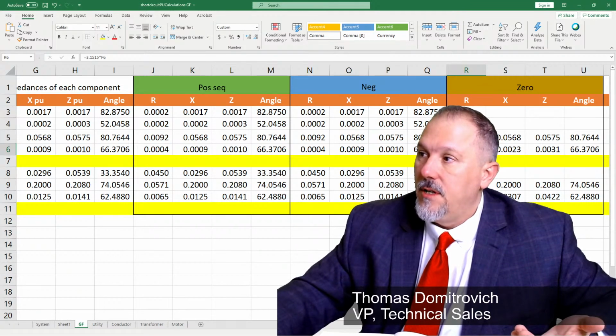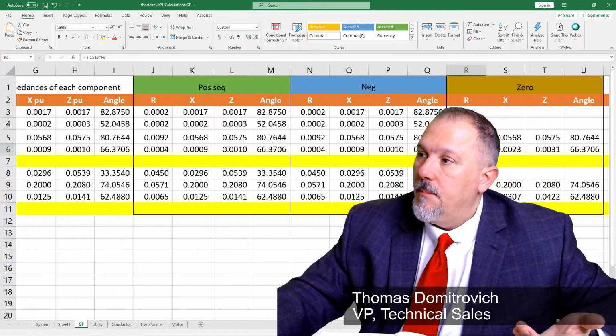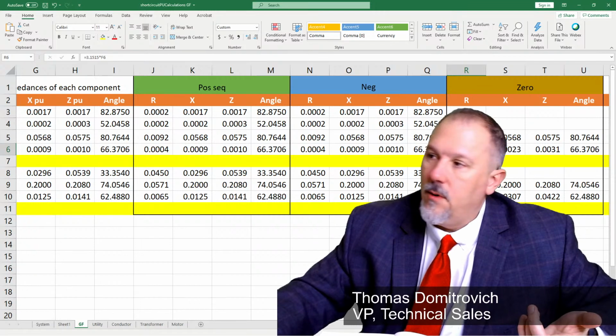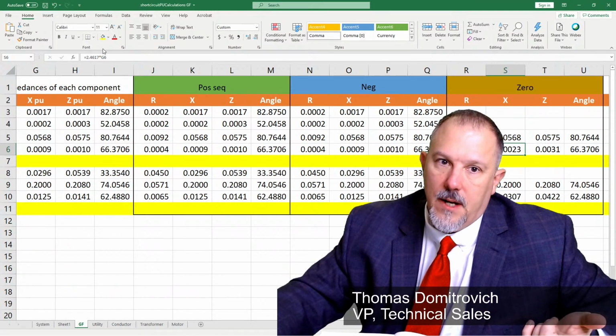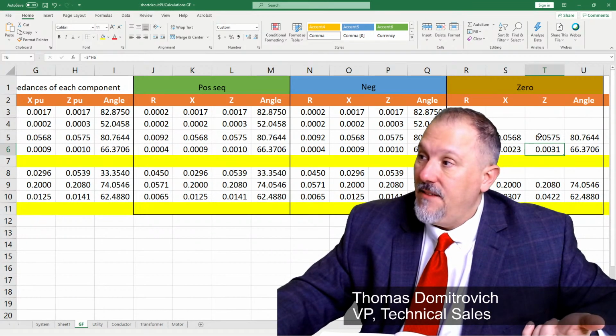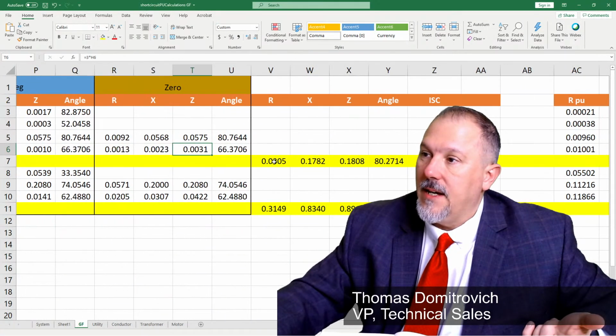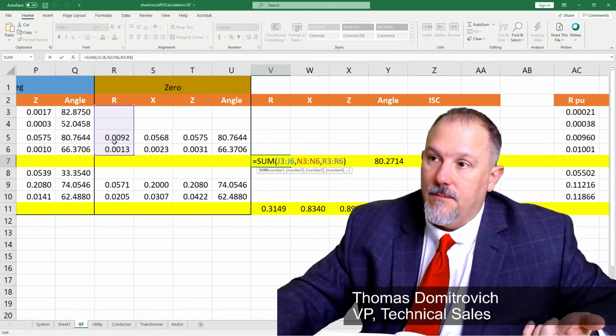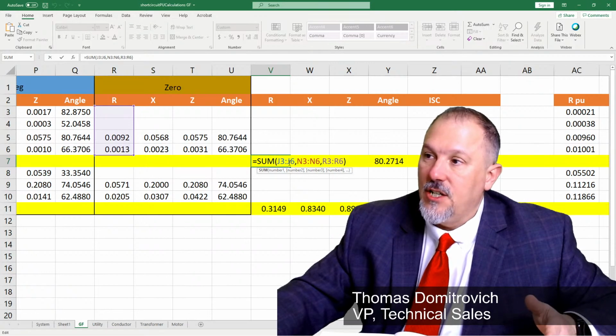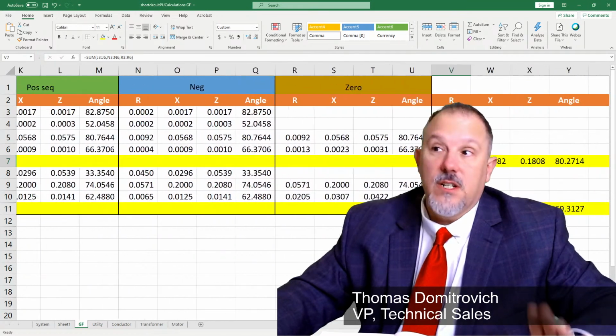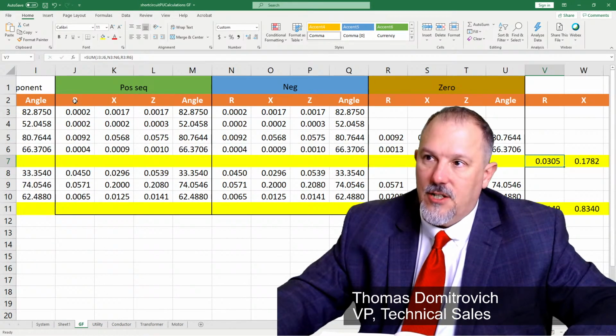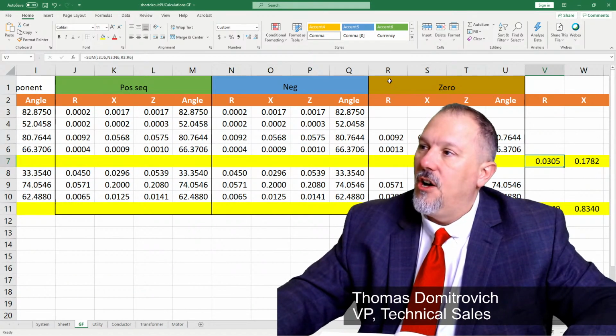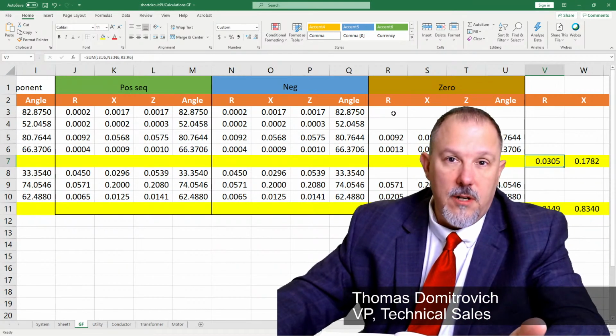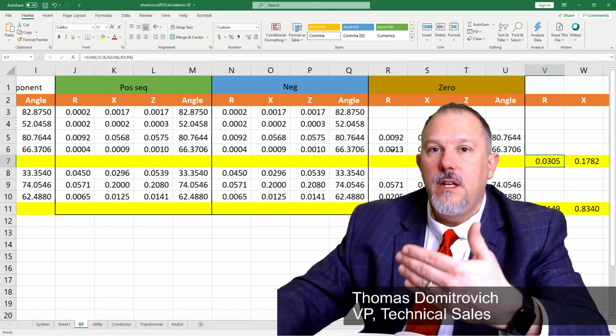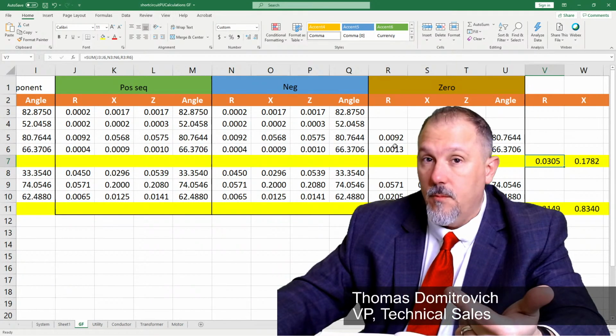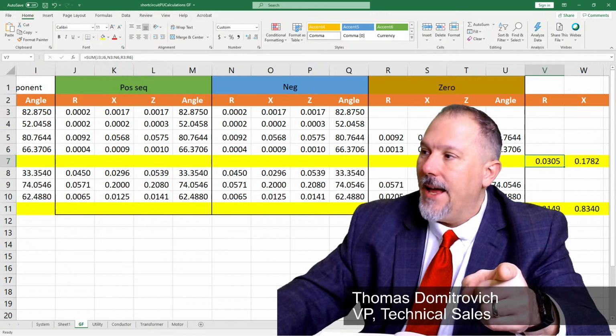The zero sequence, you'll notice that for the transformer, it's the same. But there's my conductor impedances, which I put in, the 3.1515 and the 2.4617, up here in the equation. And I have my Z values. And this is my calculating my fault current. What I did here is I summed all of my R's, my X's, and my Z's. Why did I do that? Because these are all in series. I added all of my R's for the positive sequence, all of my R's for the negative sequence, all of my R's for the zero sequence, but we didn't include the utility and we don't include the conductor on the primary of the transformer. We only include the zero sequence for the transformer and the secondary conductors for bus A. So I added all of those up.